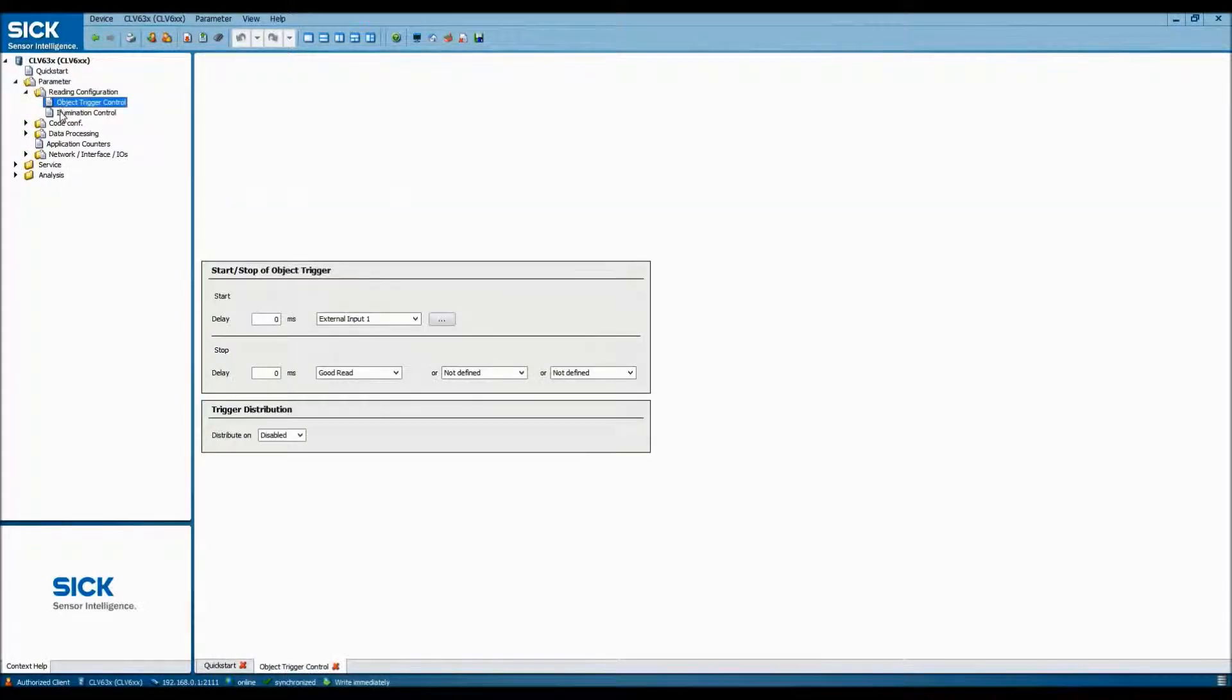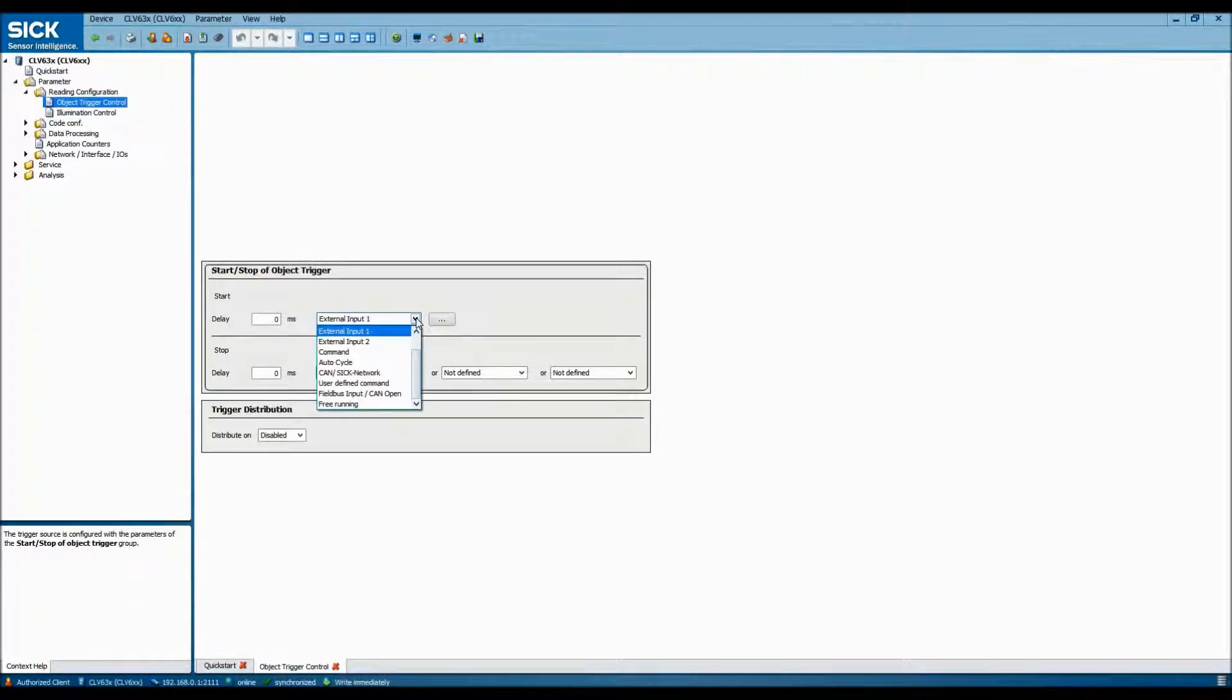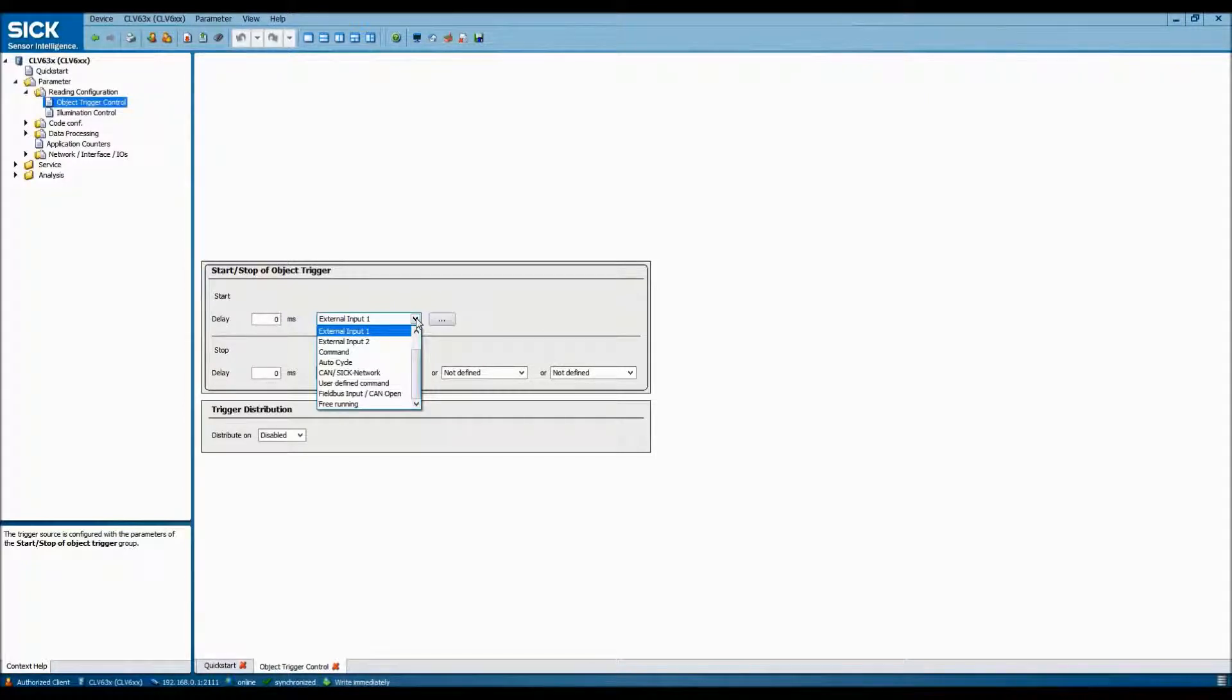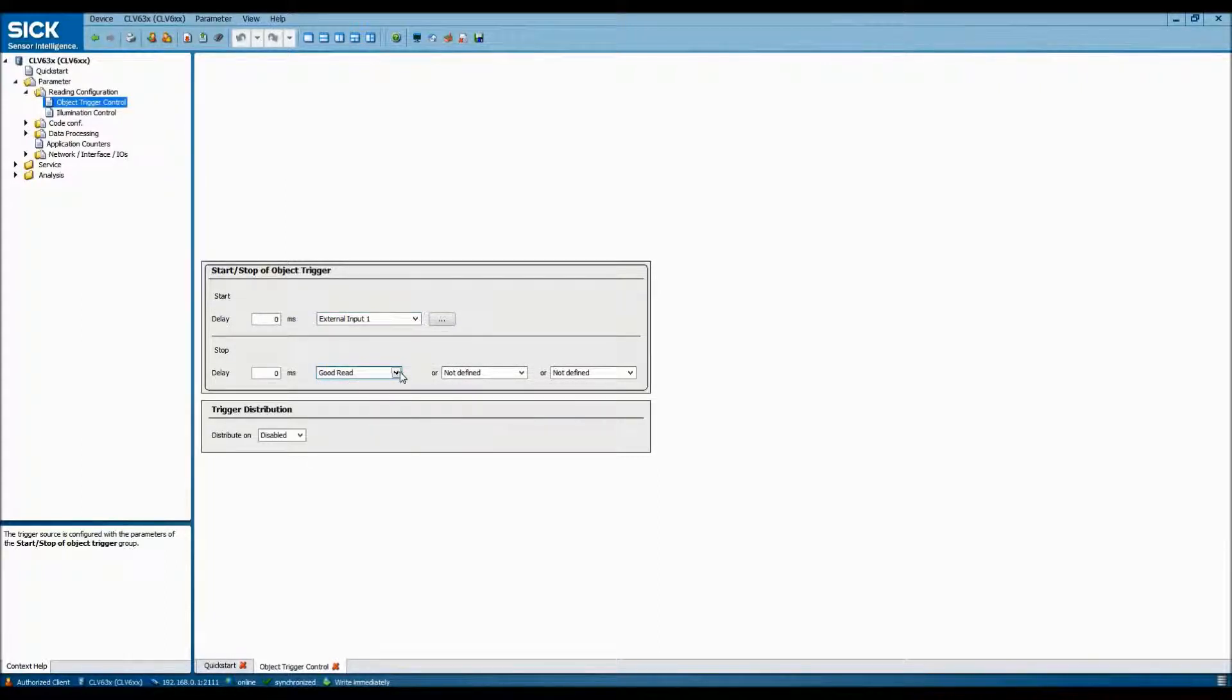As we went over earlier, we have a proximity sensor that we wish to use as a trigger for when we scan a barcode, and it's wired into input 1 on the field bus module. So in the object trigger control selection area, we'll select the start of the trigger that is external input 1, and we'd like to stop reading once we've gotten a good read from the barcode scanner.